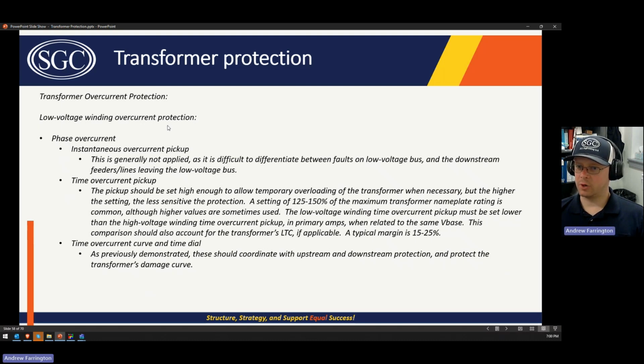Low voltage winding overcurrent protection: the instantaneous element is typically not applied, for the same reason. There's no way to differentiate between a fault inside the zone of protection and one on the bus or on an adjacent line that is close in. If you set it such that it's secure for an out-of-section fault, then it's not going to operate for an in-section fault. Therefore, there's no reason to set it, and so you just generally don't apply it.